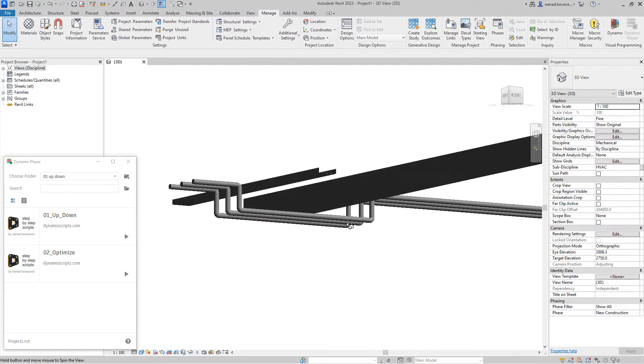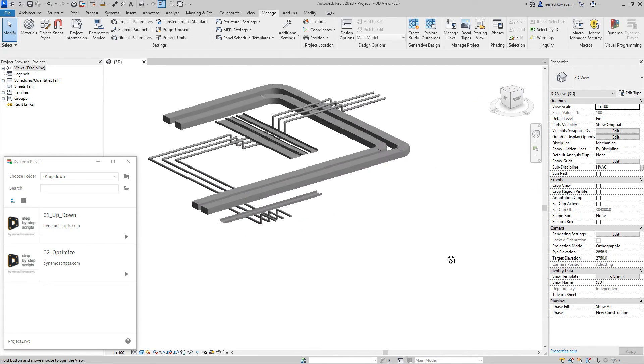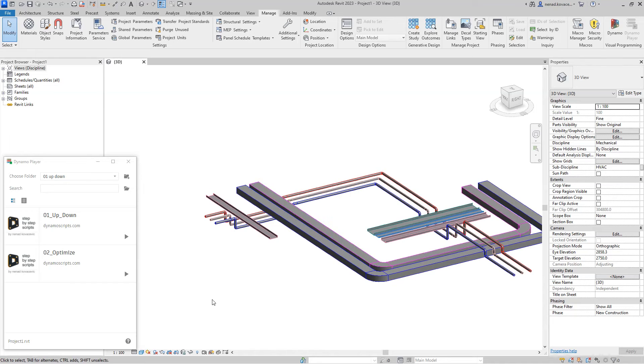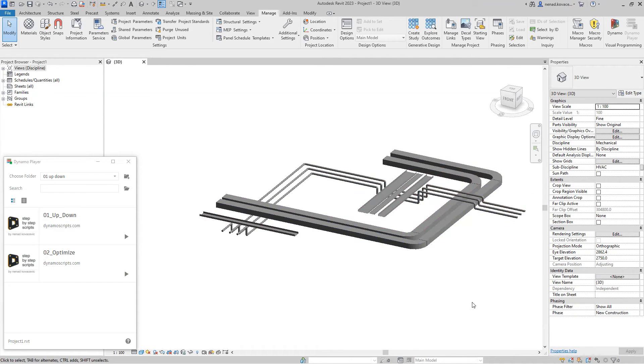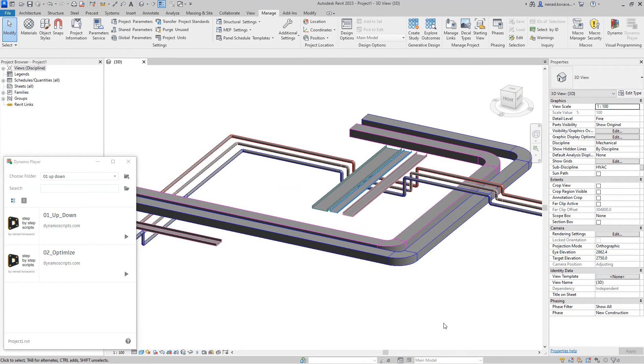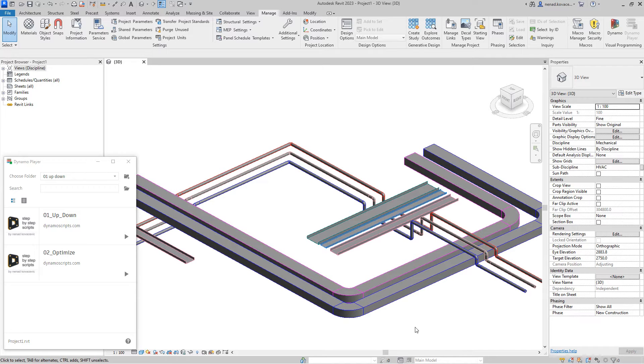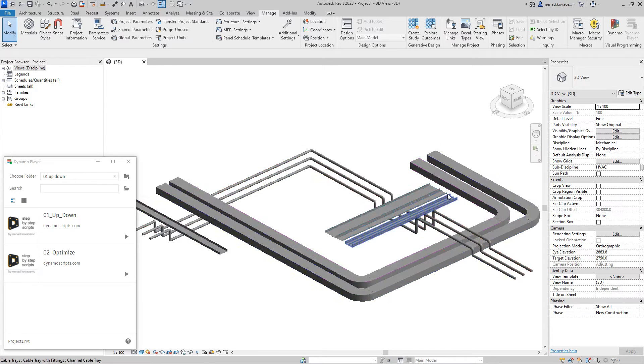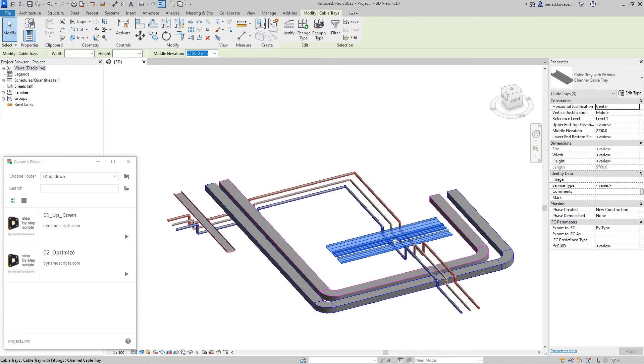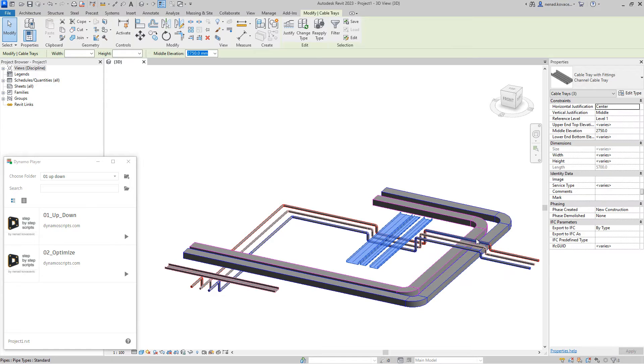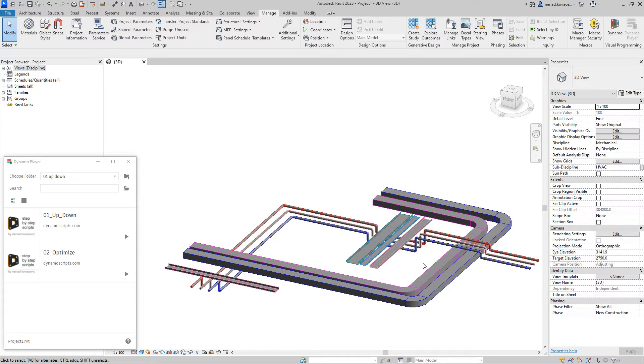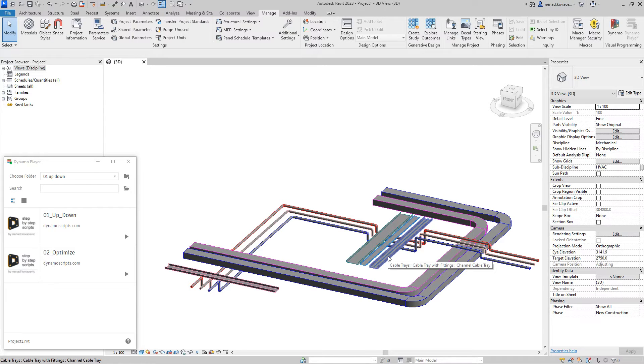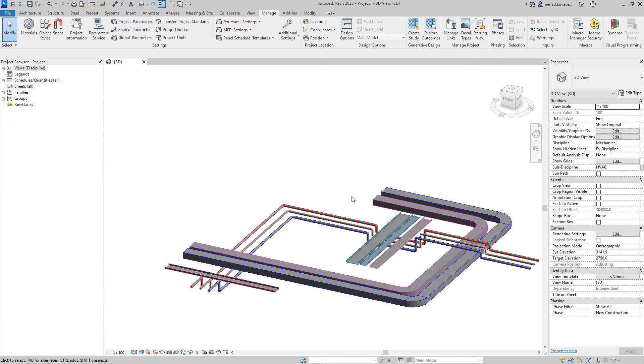And again, this is the result. Again, I do not support using all those add-in scripts, but maybe this is a first step to some intelligent solution that can help us with resolving clashes. In my opinion, the best thing to do over here would probably be to raise those cable trays, and then if you need to skip over some installation, then you just keep those ducts and then you continue with this installation on the same height. Resolving the clashes like this will increase the pressure for pipes and ducts, and again, it will not be good for the cable trays to create a lot of elbows along the installation. But okay, now I will show you the script just to see how I did this. And that's it, thank you for watching.